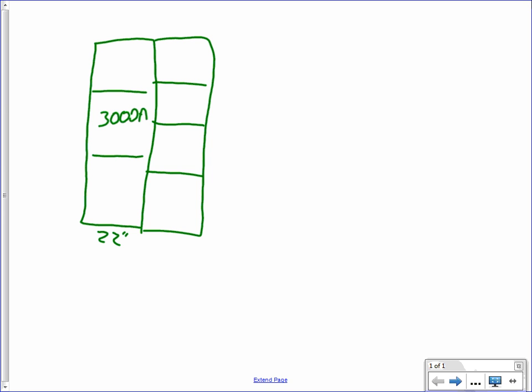Each one of those cubicles will accept, depending on the depth of the board, if it's standard 72, we can definitely put four 1600 amp breakers in a section. Possibly 2,000 amp, but we might have to force it to 7 feet deep. It's all because of wire bending space, because the deeper we go, the more cable space in the back.